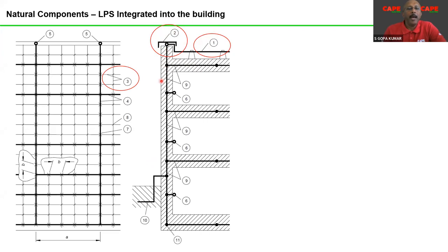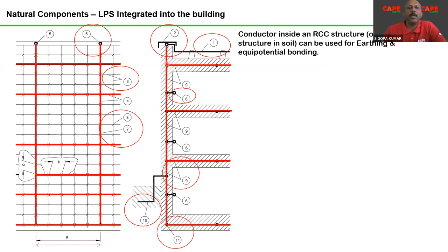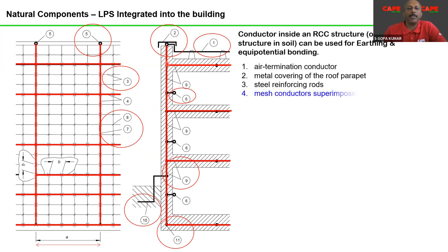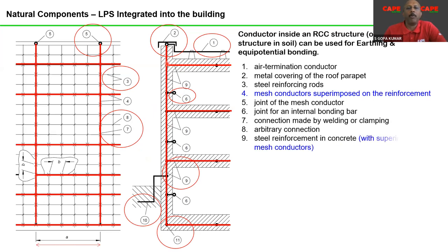Then the black color line, which I have changed to red, means an additional conductor embedded inside concrete. It's an additional conductor embedded inside the concrete. Now, you have item number 6, which is basically some kind of equipotential bonding connections. Please understand that this is a typical picture. Each of these components has to satisfy its requirement. There are several technical requirements. It is not like you put a conductor from top to bottom of the building and your job is done. It is not like that. So basically, item number 9, steel reinforcement in concrete with superimposed mesh conductor.